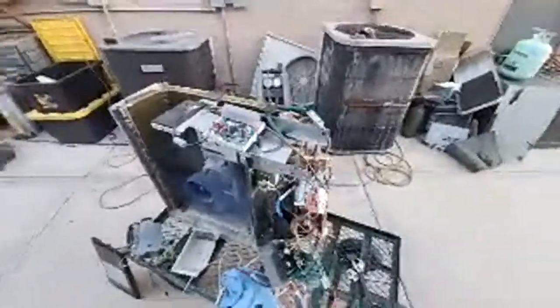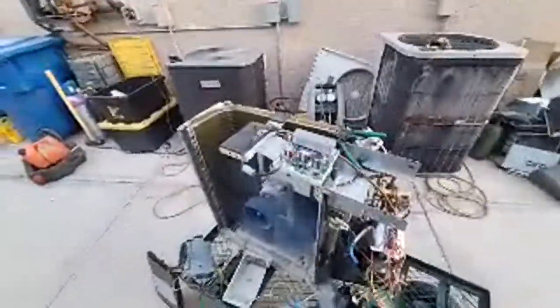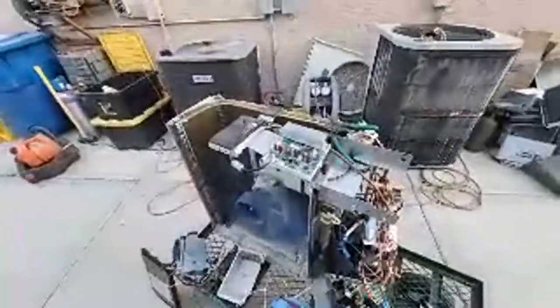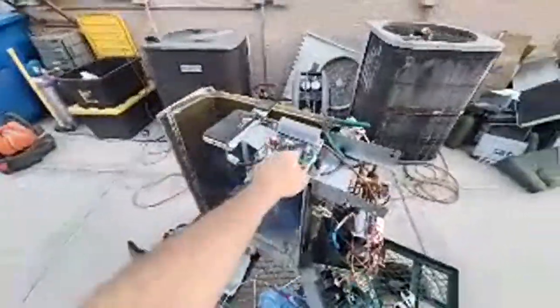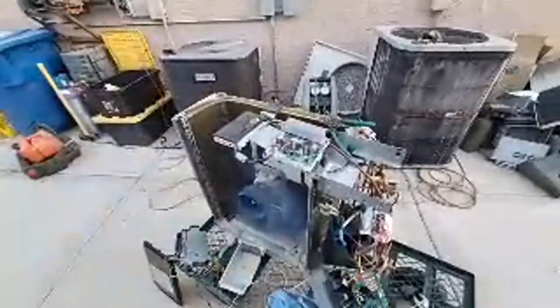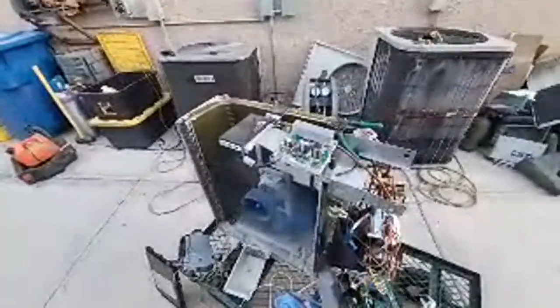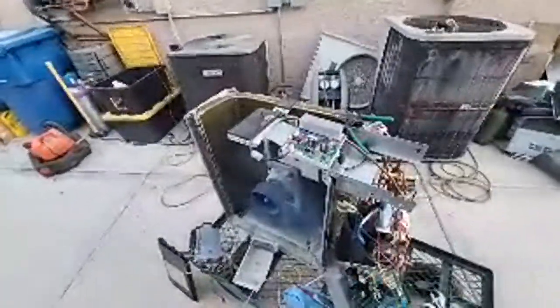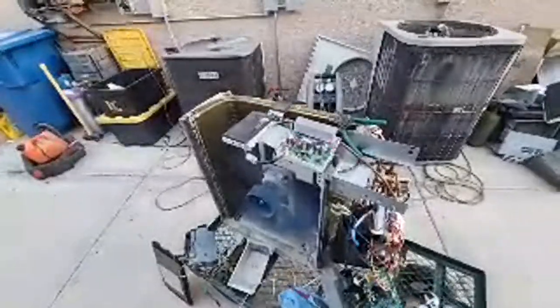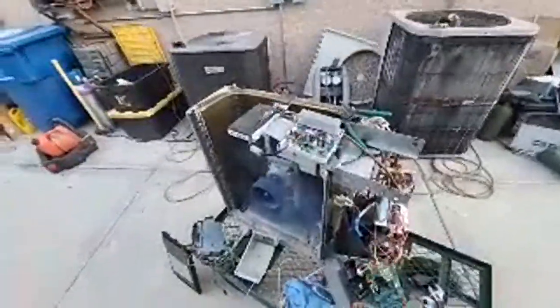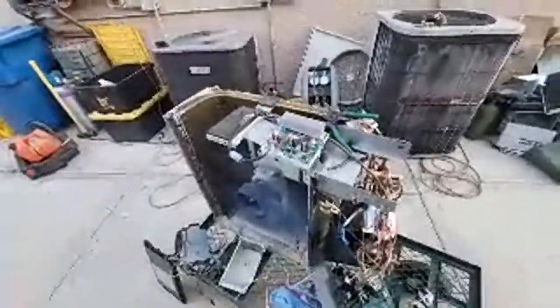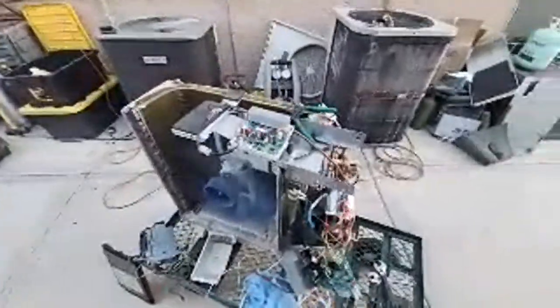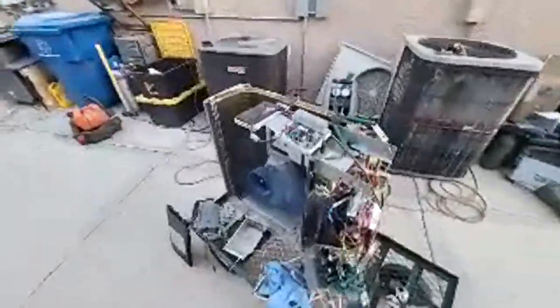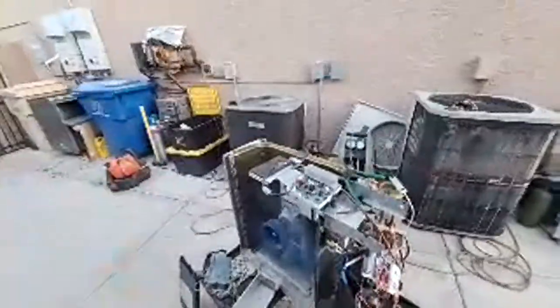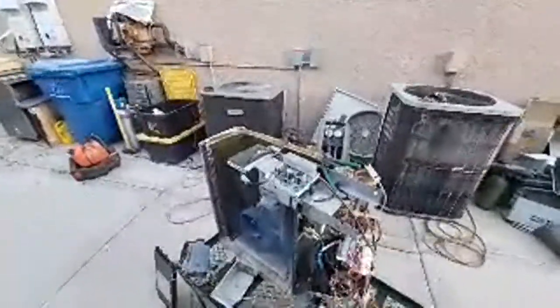And I'll tell you what, I know that this messes things up. Sorry about the F-bomb. But we have like all these Daikin units we had lots of trouble with, and their inverter boards, I know inside their fan coil units, whenever we would plug in the power, it would do that. You go pow, you plug them in, and every job that the last company I worked for that was installing those Daikins, every job they installed those on, they had 15 amp fuses, well over the rating for like little 1 and 2 ton small fan coils, like 12,000 BTU, 24,000 BTU, whatever, 15 amp fuses on 230 volt, 208 volt, single phase.